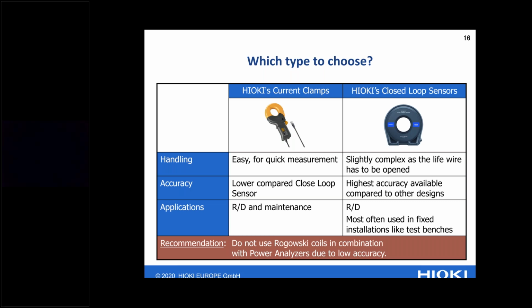In terms of accuracy, closed loop sensors are more accurate because, compared to current clamps, you don't have the small gap to clamp on. On the other hand, the downside is you need to cut the cable first, or do the wiring through the closed loop sensor before fixing it to the inverter, battery, or motor drive system.